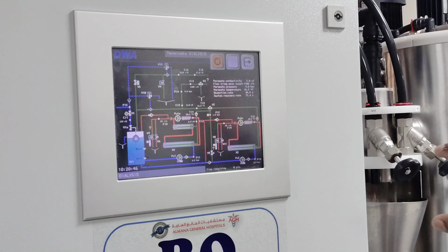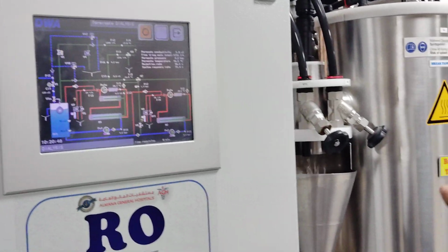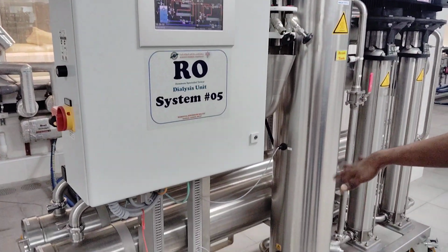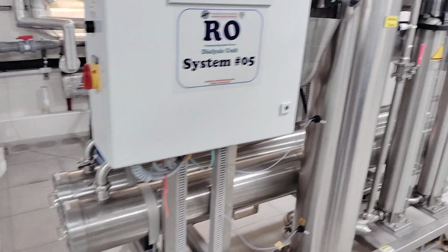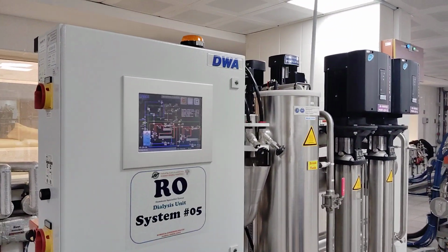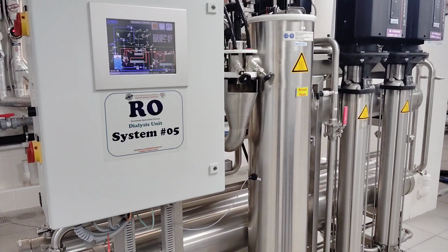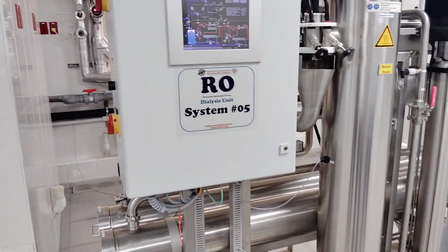Part of the water will go to the drain. Excess, high concentration water will go to the drain, and low concentration water will go to the casing. That's how we come to know that the membrane will try to remove the particles and encrustings, and also try to improve the water quality and make good quality water when it passes through the membrane.